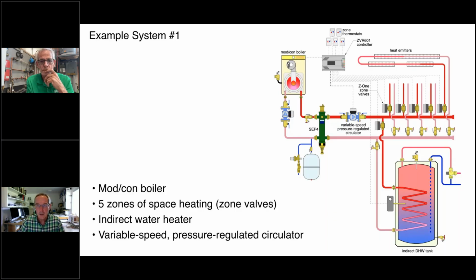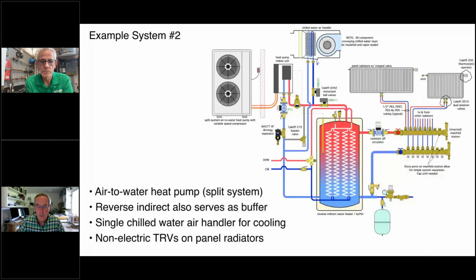We're using one of the Caleffi zone control boards here to manage the wiring. So all the thermostats and all the zone valves and even the circulator wire back, and also the boiler. This is kind of the hub of the control system. So that's a basic system. Here's one with a split system air to water heat pump. It's using a tank here that's a reverse indirect, where we're heating the fluid in the shell of the tank.